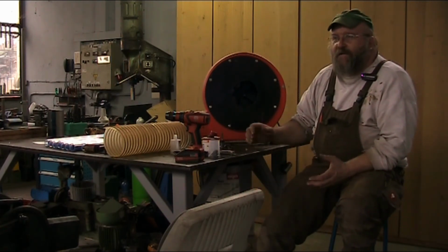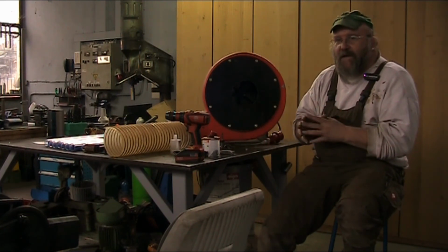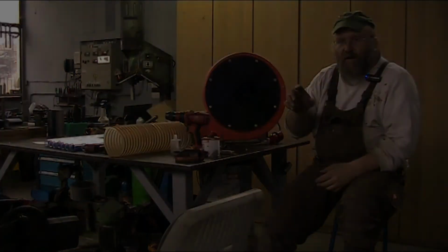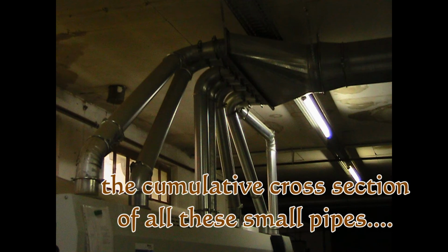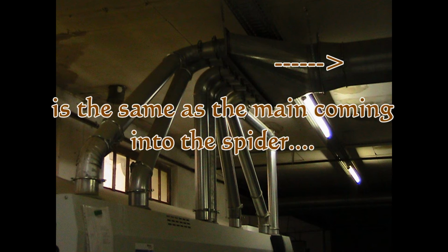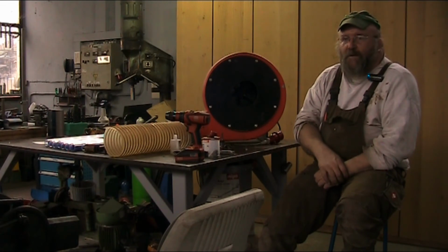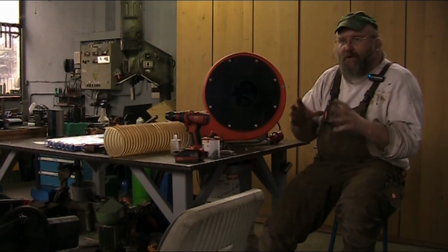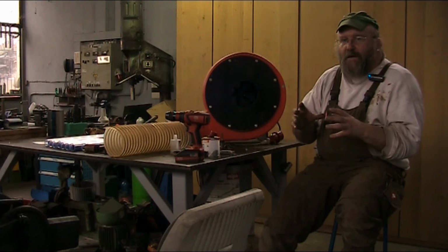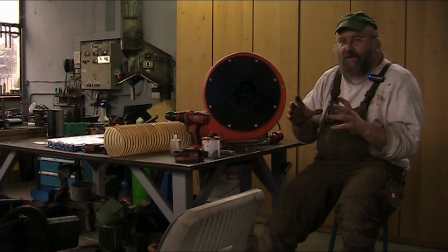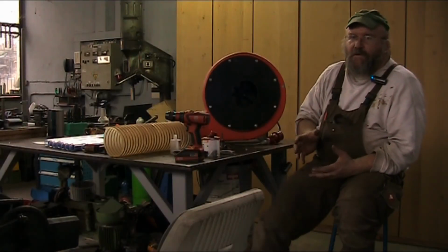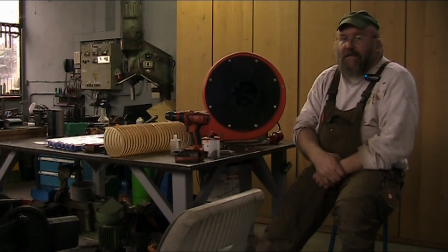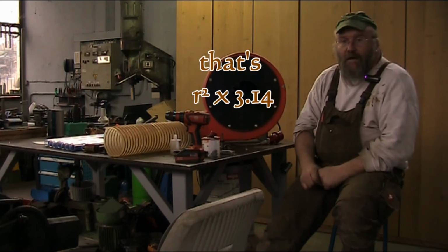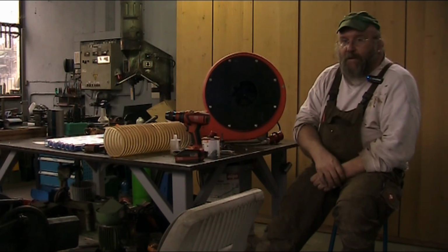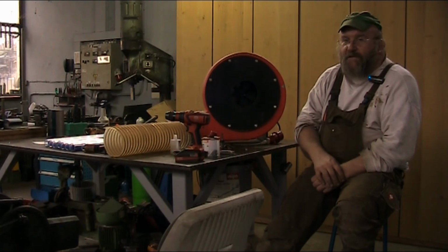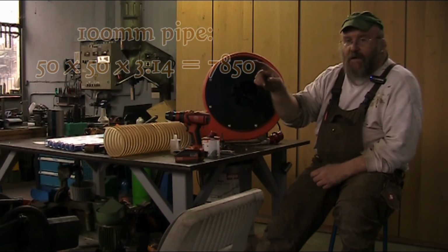So if you can avoid it, you want to maintain, if you're necking it down, like for multiple outlets, like for right here, you want to make sure that you're still covering the same cross section. When you double a pipe size, say if you go from 4 to 8, you're increasing the cross section of the pipe by approximately a factor of 4. So in order to get the cross section, you need to take radius squared times pi. So if you've got a 100 millimeter, let's see, we'll put it up right here. I don't have this stuff all in my head, and trying to figure it out on the fly is kind of tricky. So here's the cross section for a 100 millimeter diameter pipe, i.e.